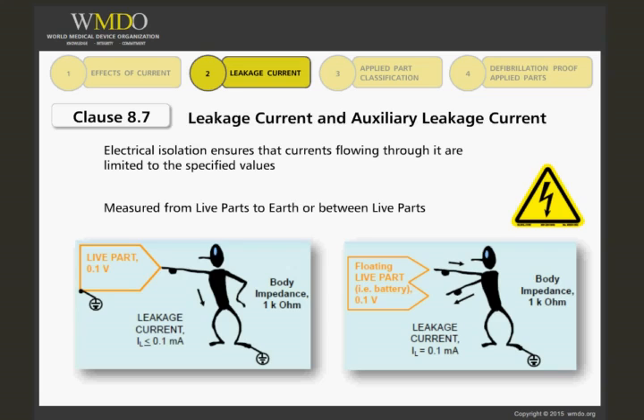The left side shows current flowing from a part with 0.1 volts through the operator or patient to ground. The right side shows current flowing between two potentials of a floating part, such as a battery-powered device. This is also called auxiliary leakage current.